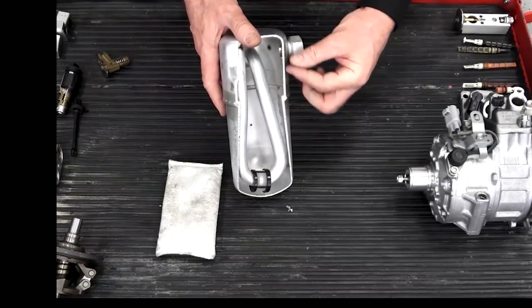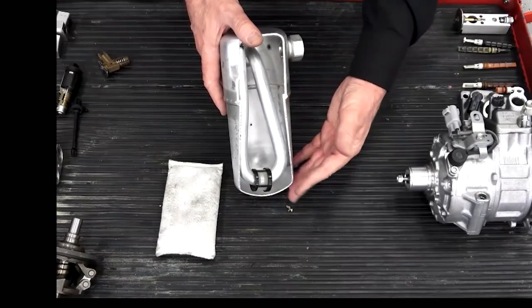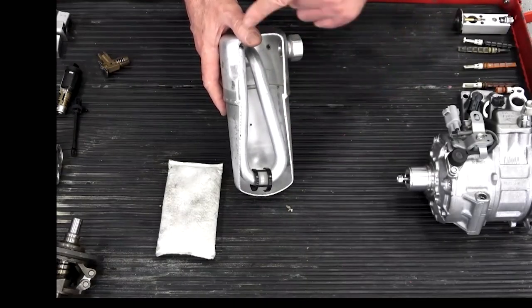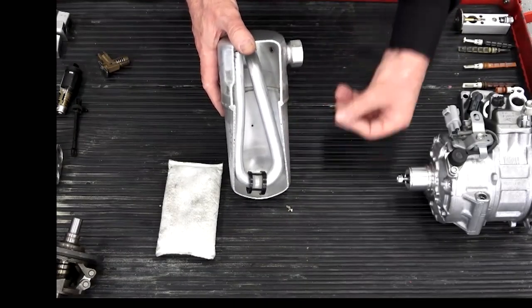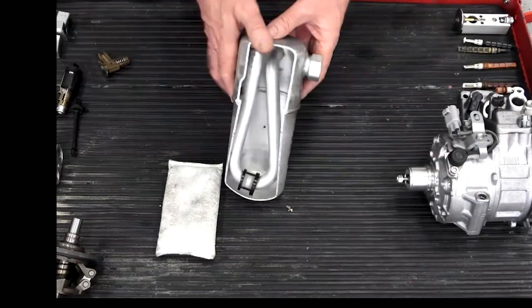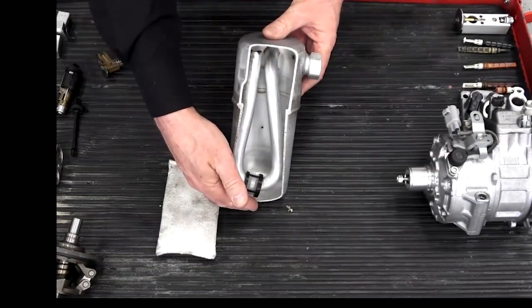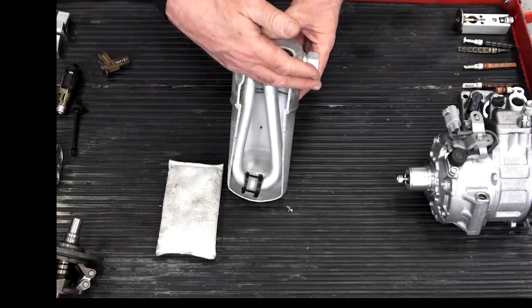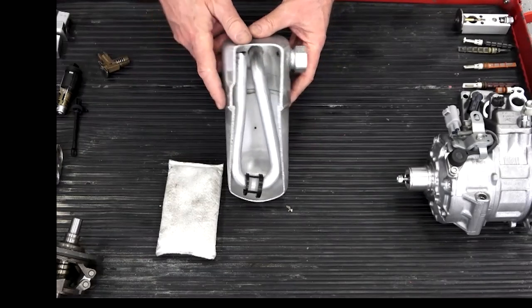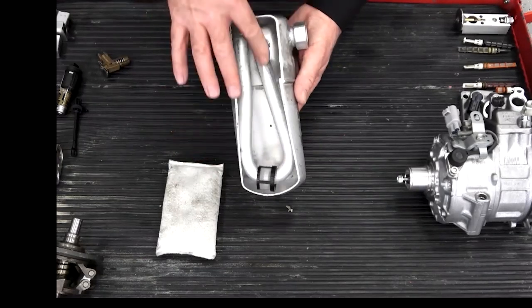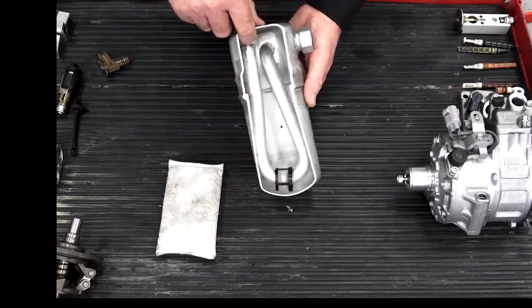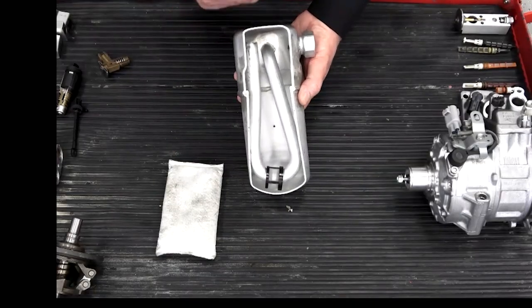And don't forget that liquid refrigerant is carrying the oil. It will be carrying the oil that's circulating in the system. It'll carry that oil up and out of the evaporator and into the accumulator, and the liquid with the oil will drop to the bottom of the can. The refrigerant gas, of course, goes to the top of the can. And this piece here we call the J tube, and you can think of it as a snorkel.